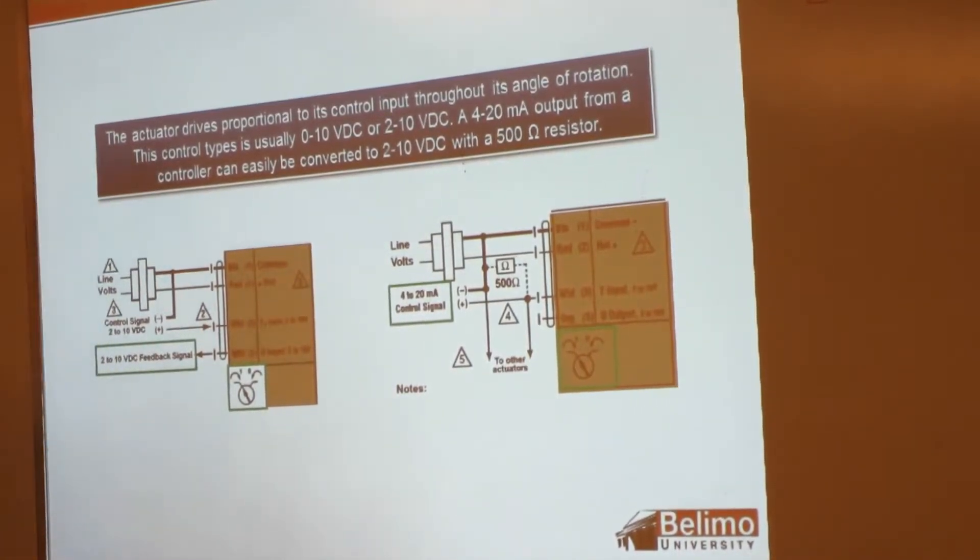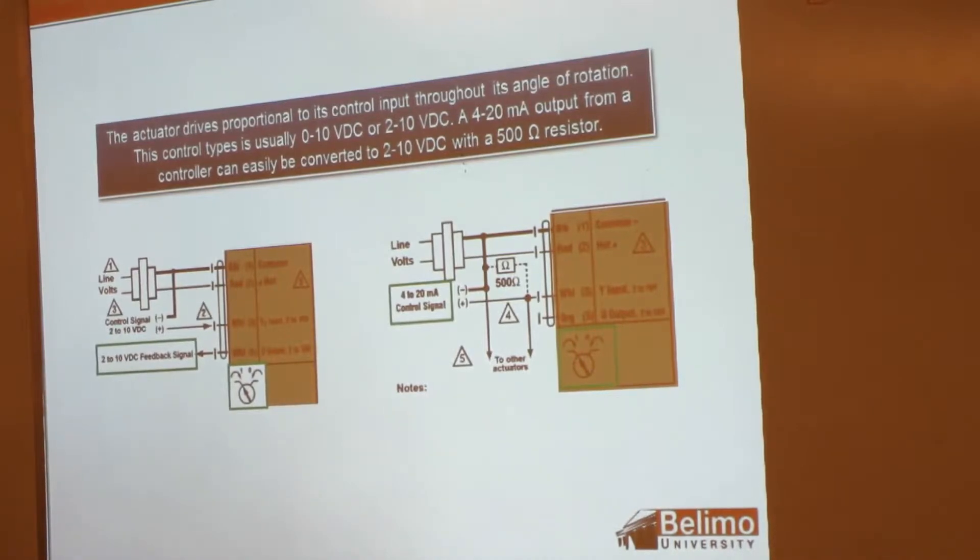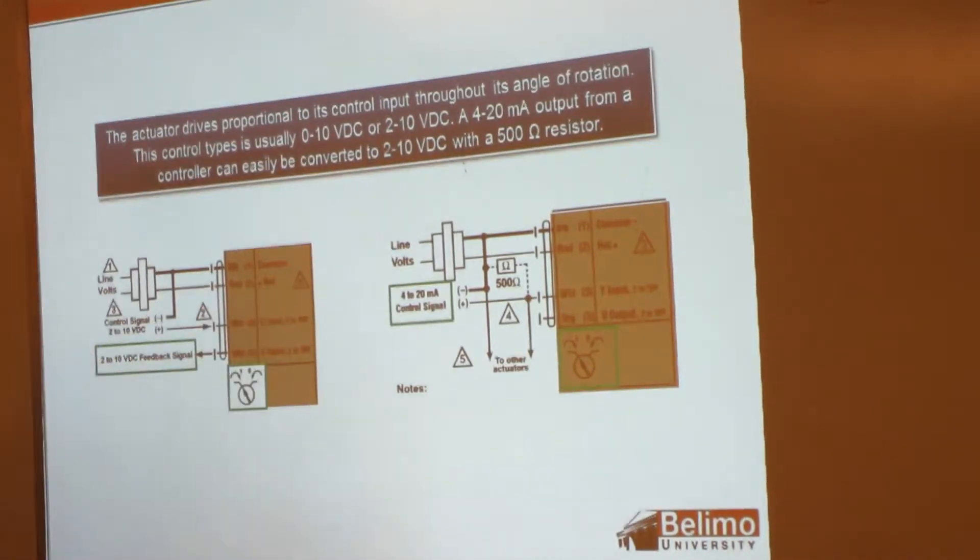With proportional actuators like these, we're using 0 to 10, 2 to 10, 4 to 20 with the Belimo actuators. If you want to do 4 to 20 you need a 500 ohm resistor. You don't have a switch on, we do not have a switch for the 4 to 20, we need a resistor.